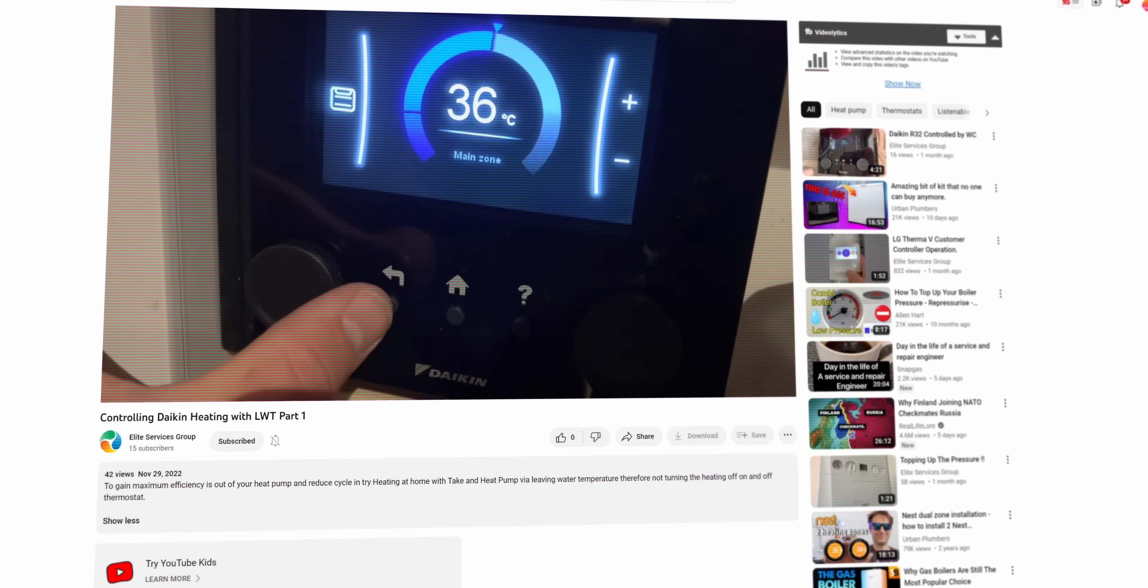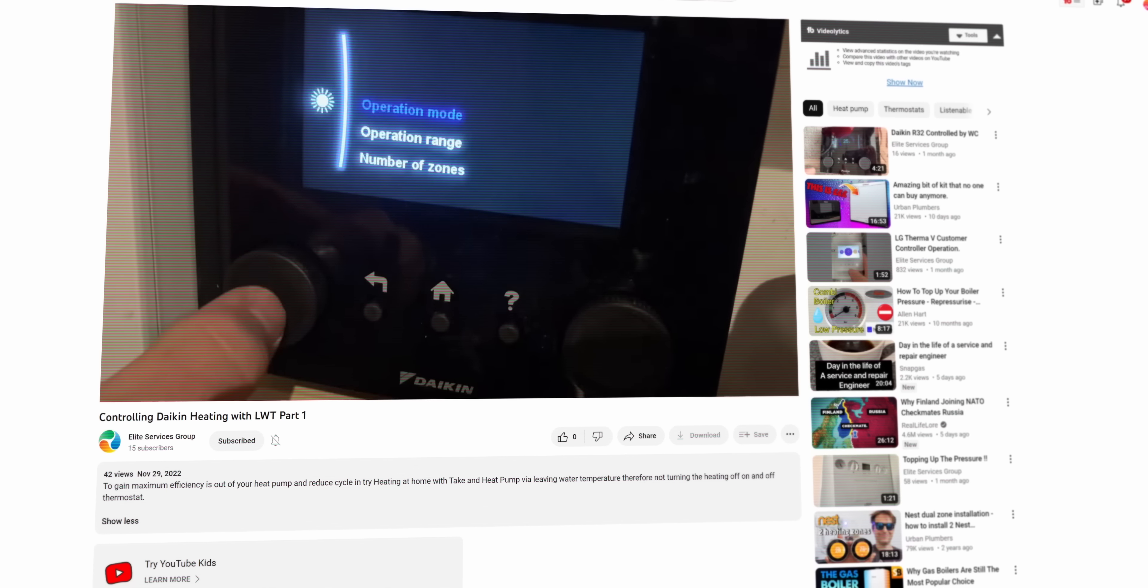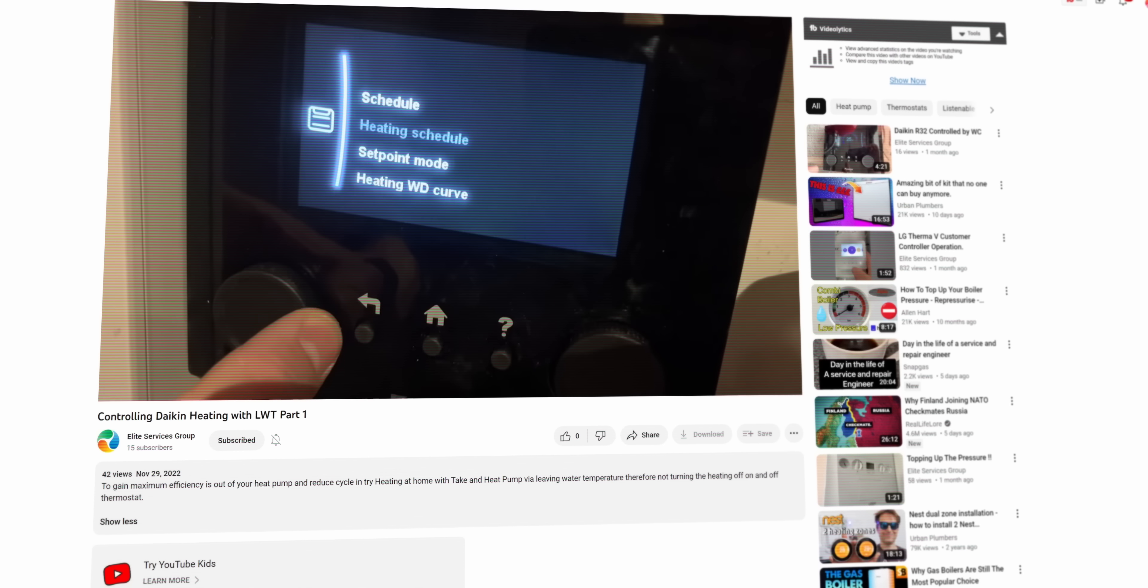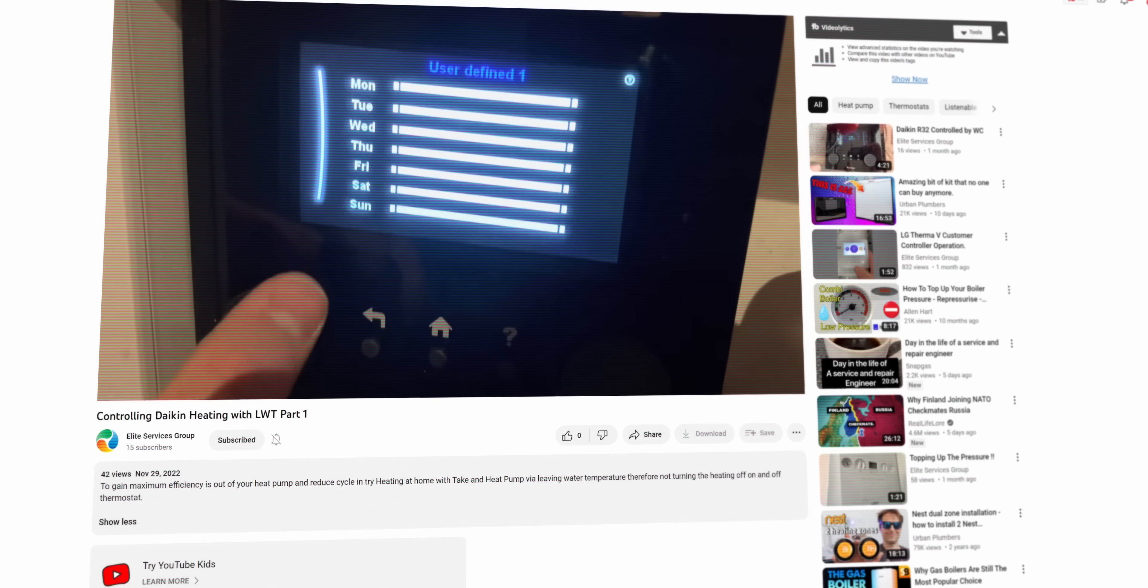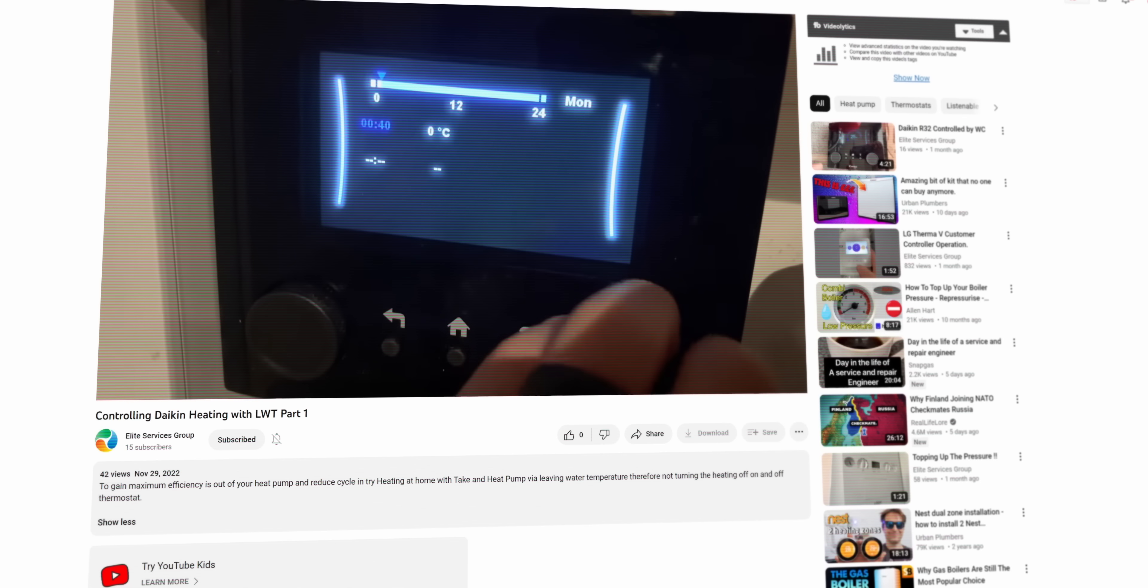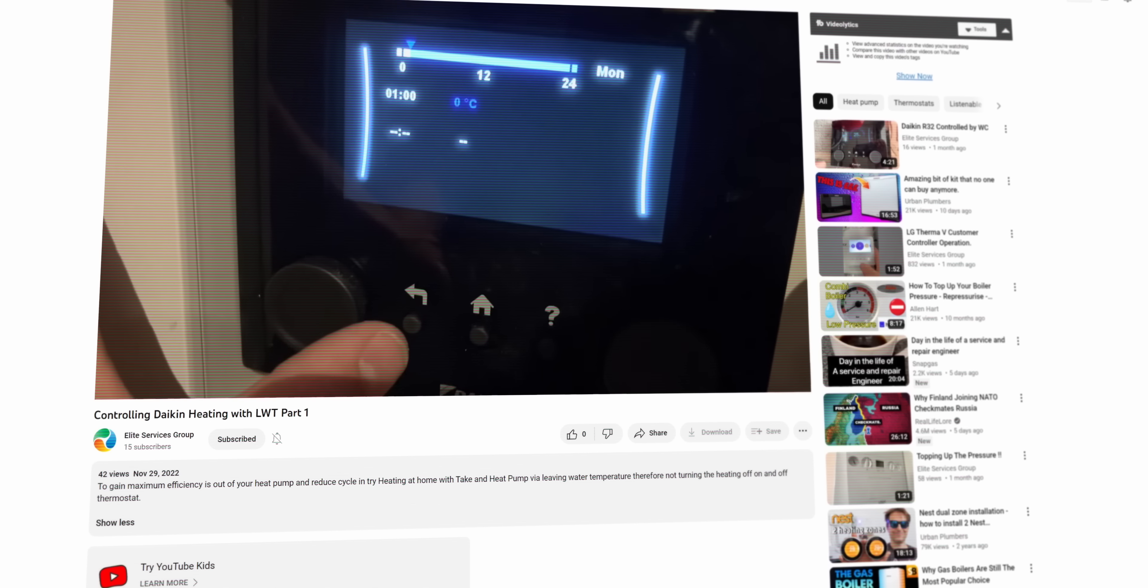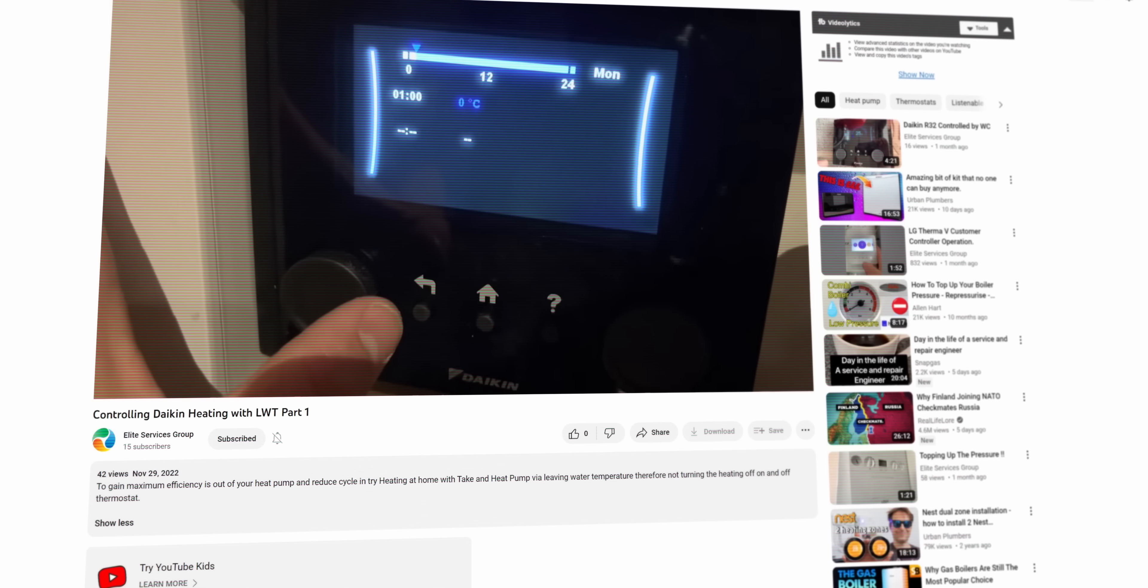If you find that you want to have lower flow temperatures during the night for a cooler temperature during the night, you can add a schedule. If you go to main zone schedule, you can add a schedule that will bring up the heating schedule. Then you can edit that and state what time and what plus or minus flow temperature you want. So during the day it might be zero, during the night it might be minus three or four, and that will lower it maybe down to 18-19 degrees during the night.